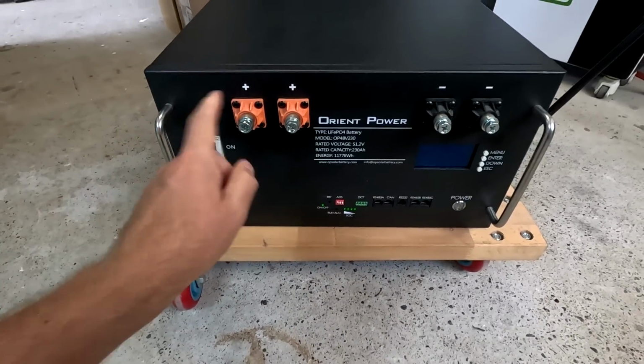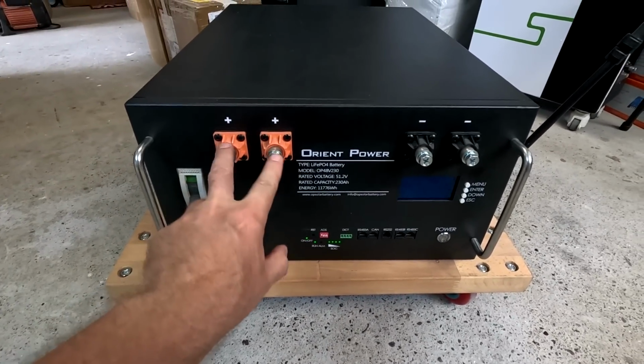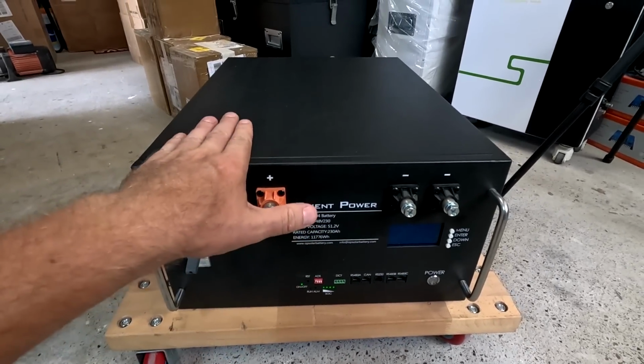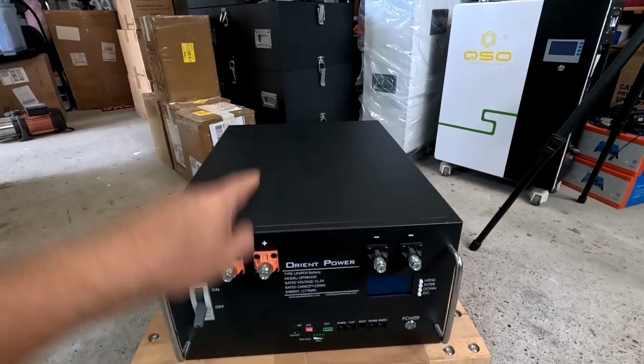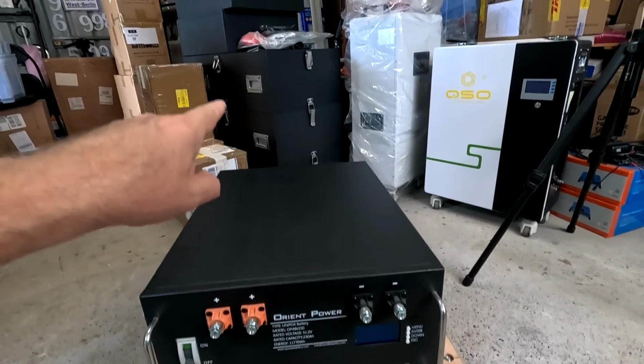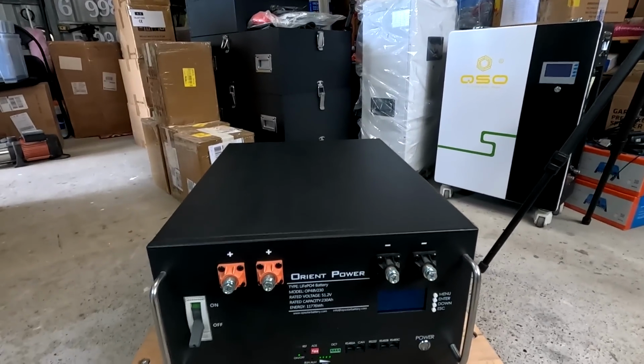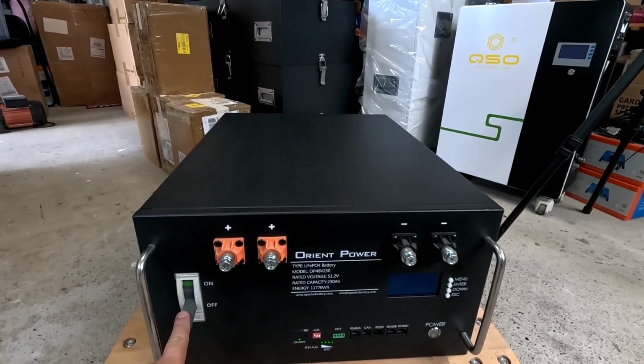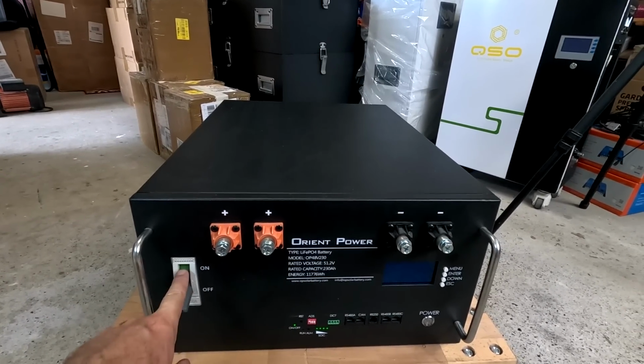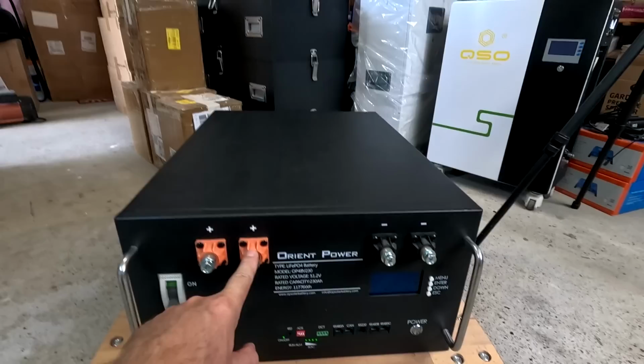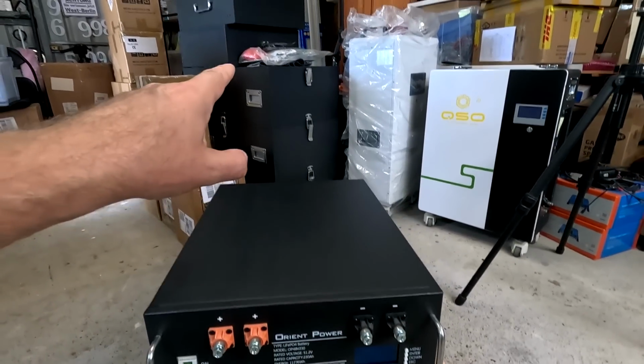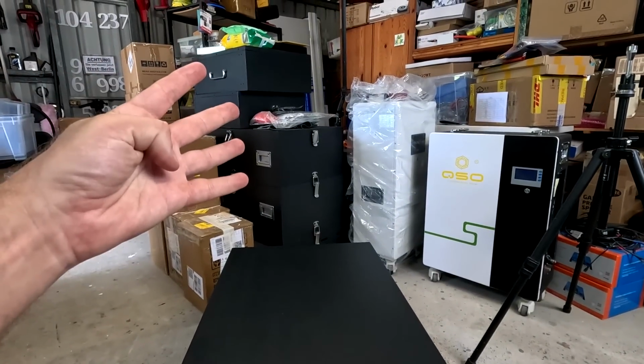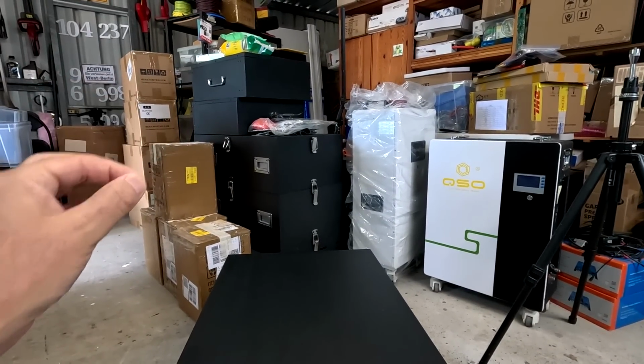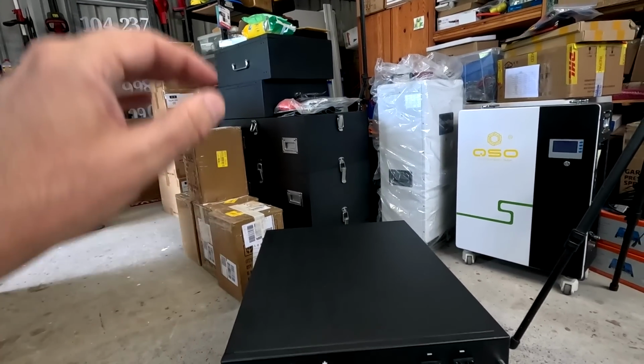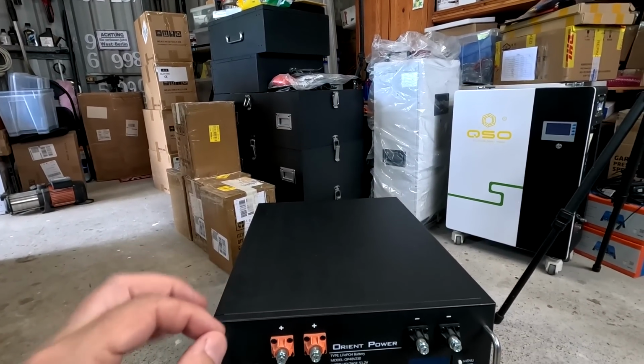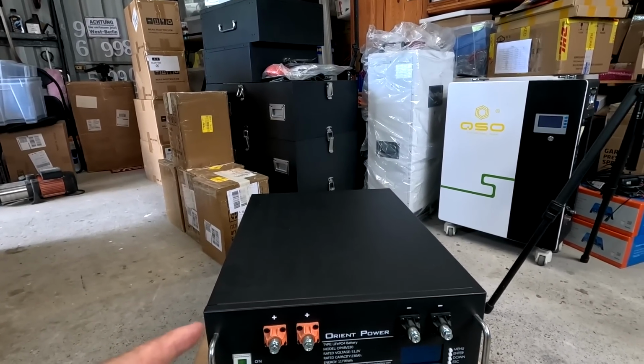And then imagine you've got double terminals here, so this is actually designed for stacking multiple of these batteries up and connecting one battery to the next, to the next, to the next. With every battery you're adding 250 amp of breaker capacity. So 250, 500, 750, and 4 batteries are 1000 amps. So you need to have a connection cable to these 4 batteries which is rated for 1000 amps.